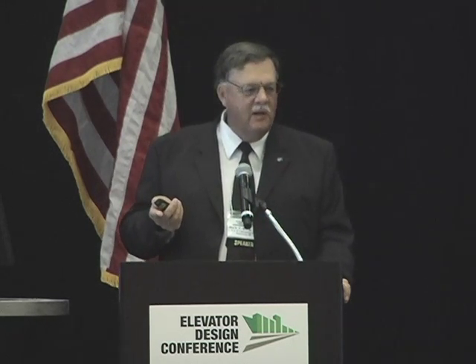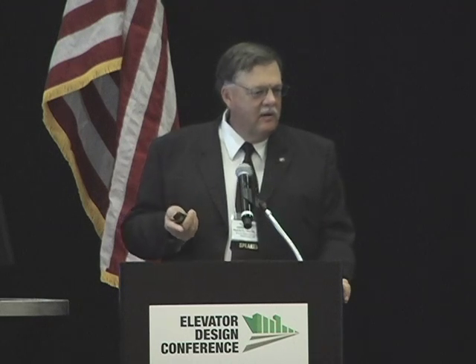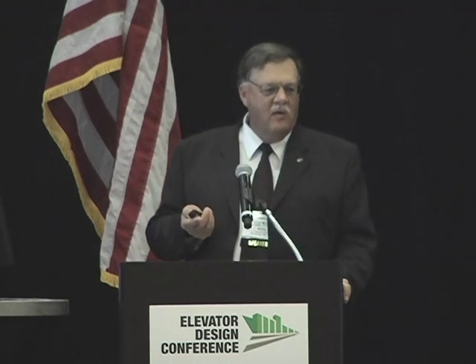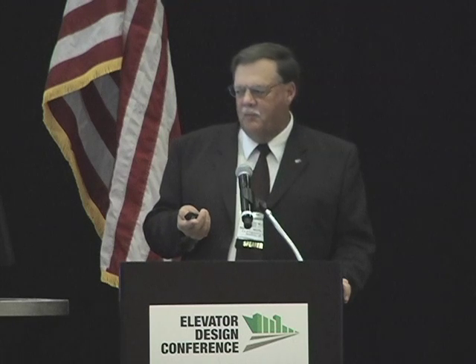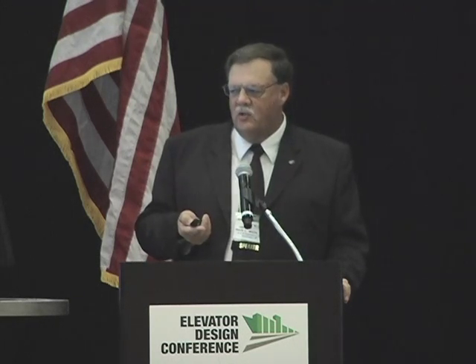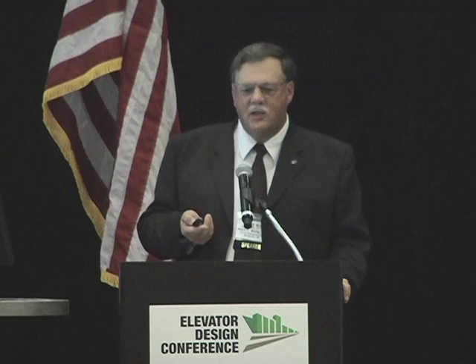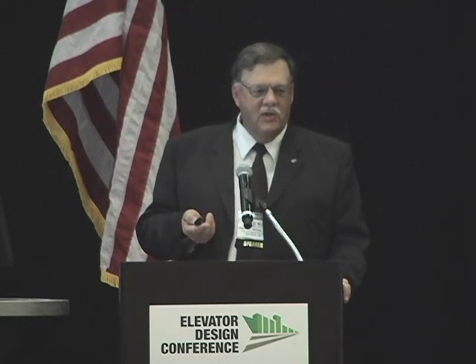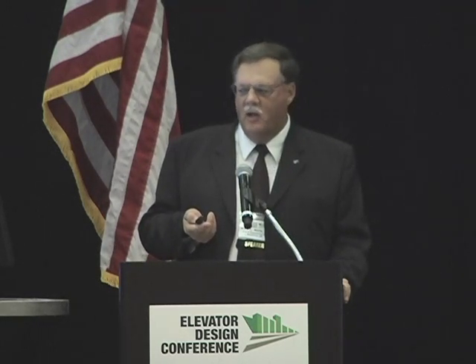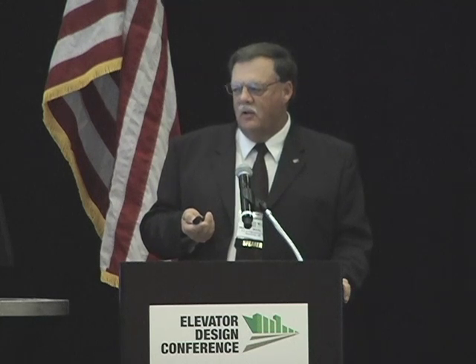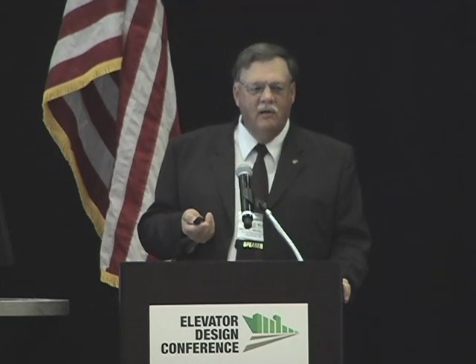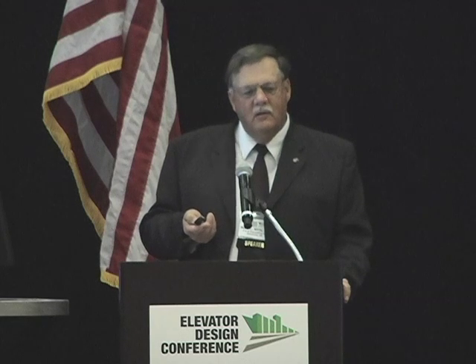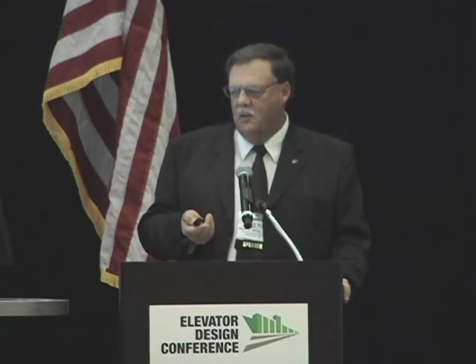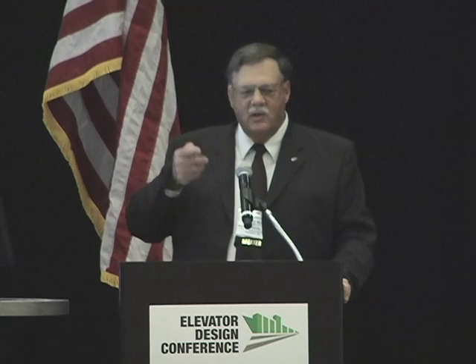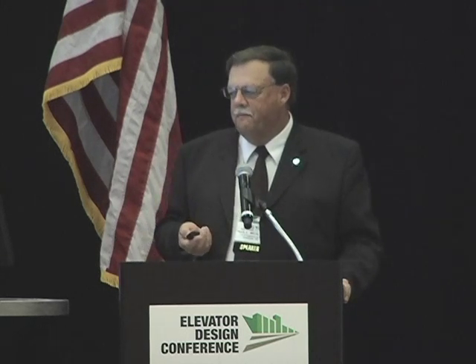You also typically see these types of voltages on trailing cables if you have a mobile ship loader. All your container cranes at most of the shipping ports run on trailing cables at 4160 or 2400. But you'll also see that in a lot of mobile ship loaders or unloaders in industrial facilities, because you can get a lot of energy through the cable to the ship loader at these voltages. That's a typical place for them. So you only see these on the very largest facilities.